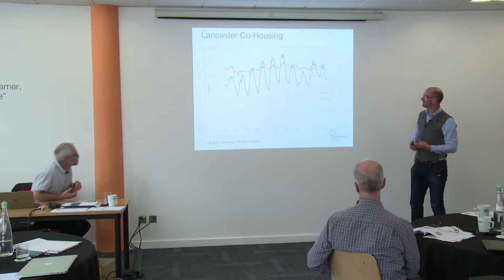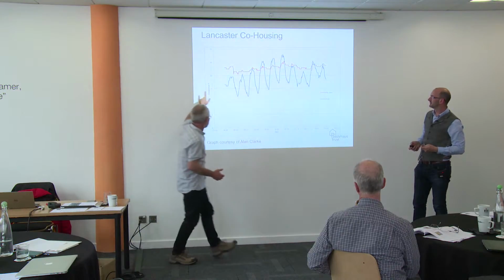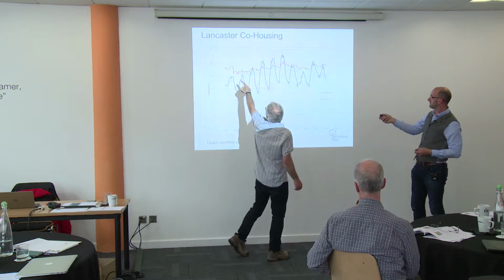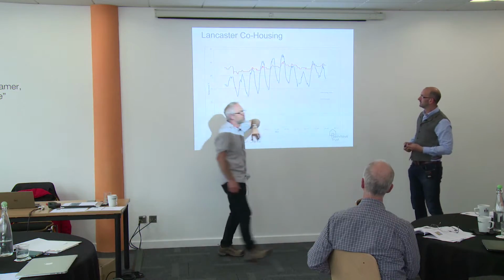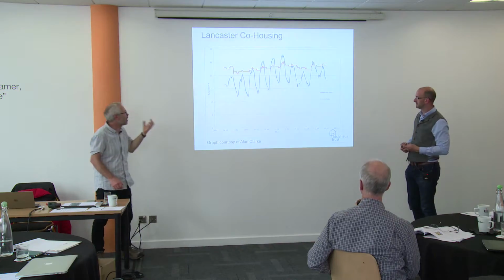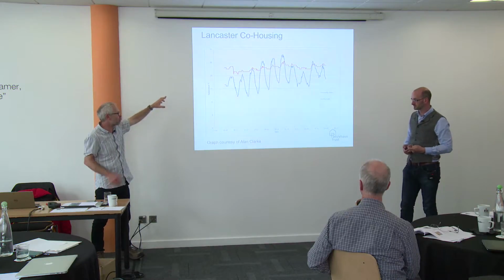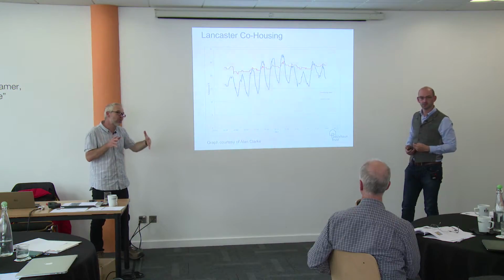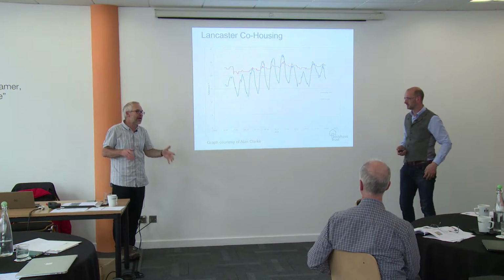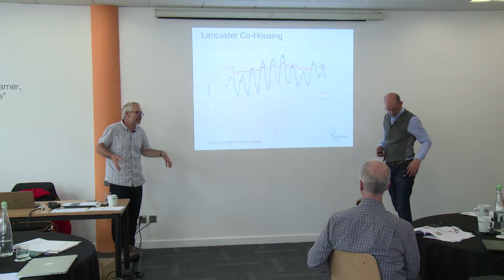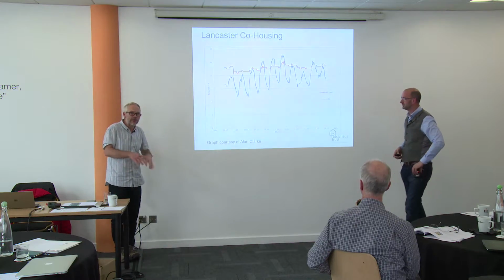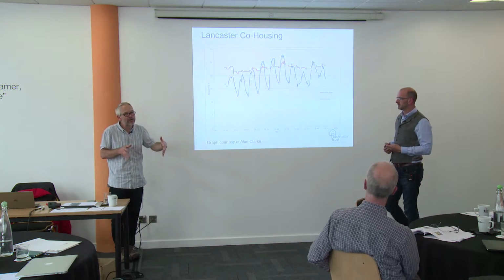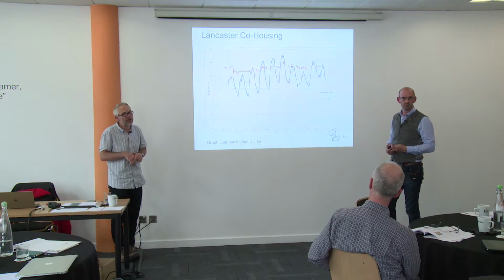We've got actually some temperatures here. We've got a couple of shots of the living room and the outside temperature. This is again July. That's the living room. It went over 25 for a few seconds in the living room. But as it said before, there's a bit more glass than we might have done, partly because they were trying to hit the 15 kilowatt hours, and they're quite small flats, so the gains are actually very high. They have a lot of shared communal spaces, with guest rooms, storage and workshops, so the actual flats are quite compact. So the internal gains will be relatively higher.